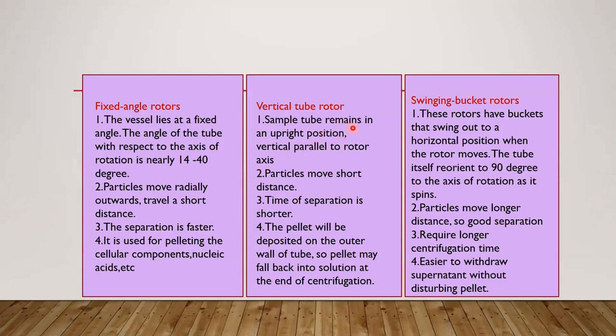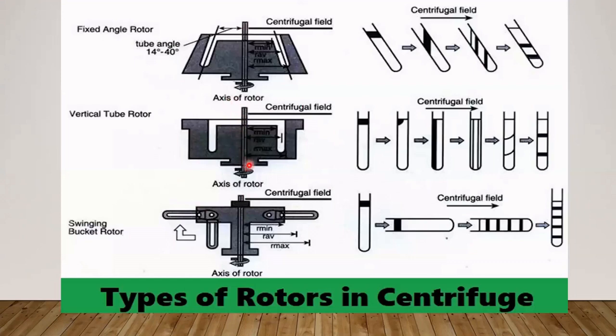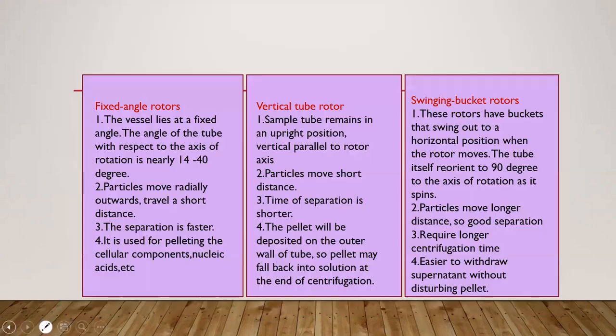The vertical tube rotor holds the sample in an upright position, that is vertical and parallel to the rotor axis. Here the particles move a short distance, so the time of separation is shorter. However, a drawback is that the pellet will be deposited on the outer part of the tube and may fall back into the solution at the end of centrifugation.